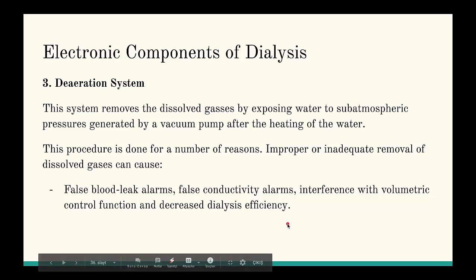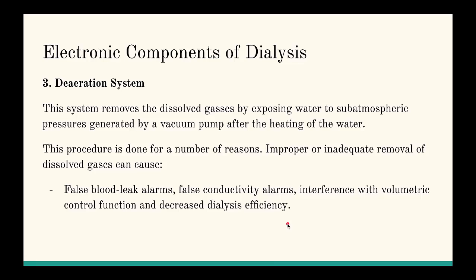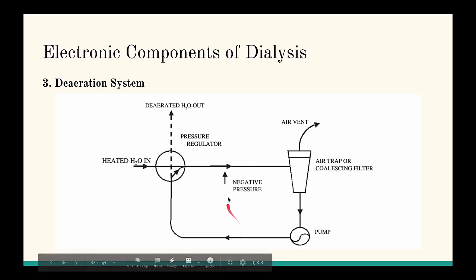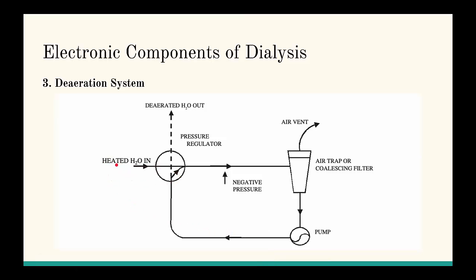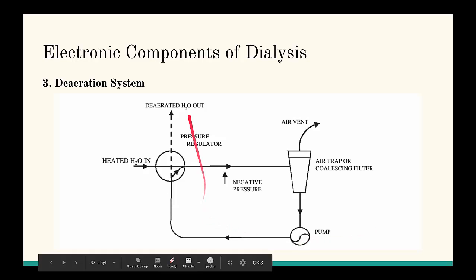So the last thing we want inside our fluid circuitry is air bubbles or any sort of dissolved air that is left inside the fluid circuit. So here we have a good image of this. We have the heated H2O water going in. There's the negative pressure, and the air trap takes out the bubbles that are arising from the fluid flow, and the pump takes the fluid that is degassed.